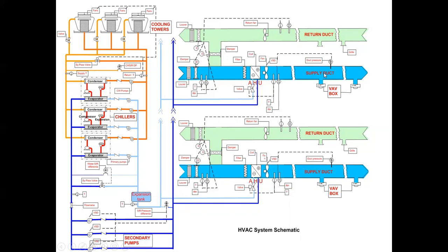I don't know. I think they did. I think it looks like this now. I think they stripped the drop ceiling out. But anytime you've got a drop ceiling, you can usually find the units by looking for the little brown water spots. That's usually where the units are. Or, I mean, it could be bad pipe insulation, or bad duct insulation or something like that. You've got condensate forming.